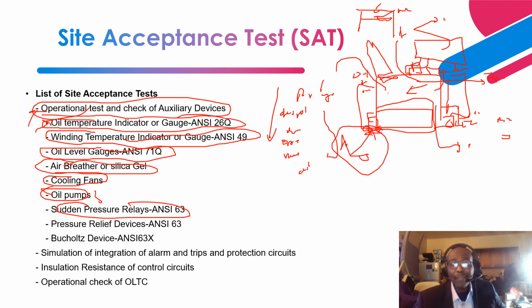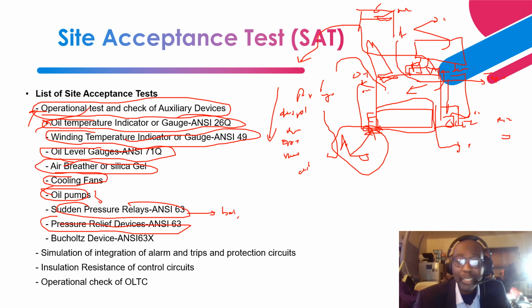On the other hand, if you should have a through fault, the high pressure wave due to the high electrodynamic forces created by the short circuit current will be sensed by the bellows of the sudden pressure relay. Next is the pressure relief device, mounted on top of the power transformer. It is basically the last protection for the transformer, based on evolving pressure, if all the protection schemes on the power transformer should fail.